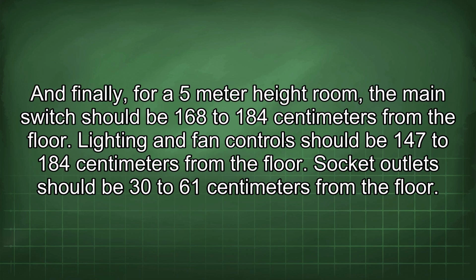And finally, for a 5-meter height room, the main switch should be 168 to 184 centimeters from the floor. Lighting and fan control should be 147 to 184 centimeters from the floor. Socket outlet should be 30 to 61 centimeters from the floor.